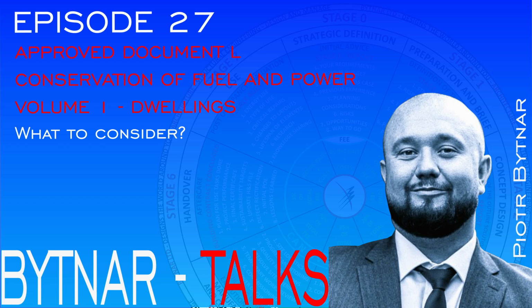B. Providing fixed building services which I. are generally efficient to a reasonable standard, II. have effective controls, and III. are commissioned by testing and adjusting as necessary to ensure they use no more fuel and power than is reasonable in the circumstances.